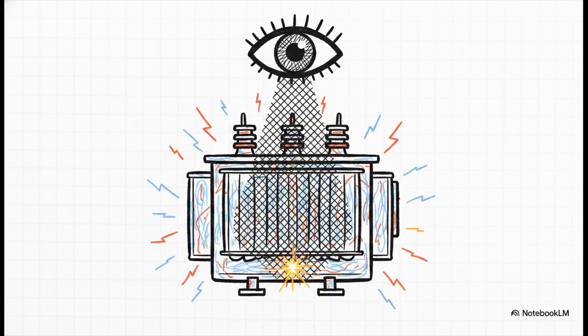A fault right next to the neutral point produces almost zero differential current imbalance. So from your standard differential relay's point of view, it's practically invisible. And that is exactly the blind spot that ground fault protection is built to close. Transformers simply cannot tolerate sustained fault current without rapid thermal runaway and, well, mechanical deformation. Leaving this unprotected creates a massive, highly dangerous vulnerability in your entire protection scheme.